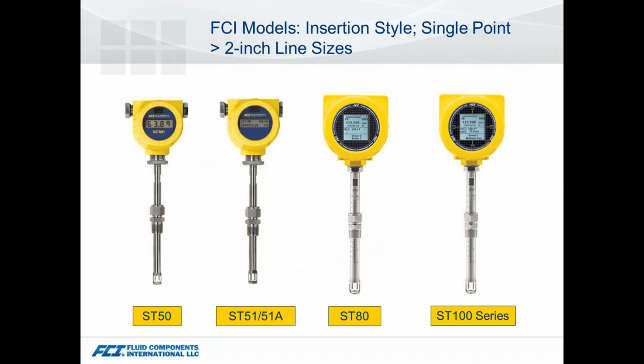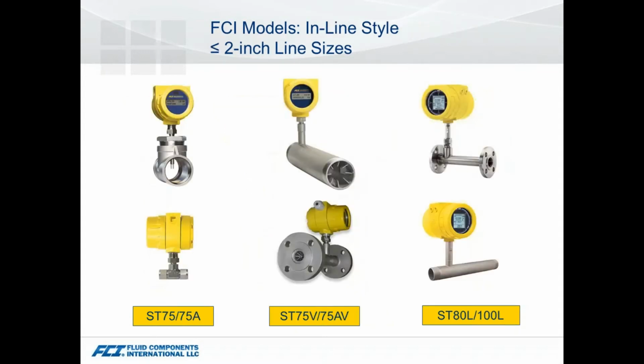For insertion styles, we actually have 8 different models, actually 9 different models if you consider the 2 variations of the ST51, 51A. These are for larger than 2-inch line sizes, 2.5 up to as large as you need to go. Just recognize that as you get to a certain line size, if you only have 1 point in it, you have some inaccuracies, but you can use them in the very large line sizes, 30-inch ducts, pipes. Then we have 4 variations of the inline style, and these are 2-inch and smaller lines, again, going from the more economical units from the ST75 up through the versions with the 80L, 100L, where you have a lot more feature sets than you do in the economical products.